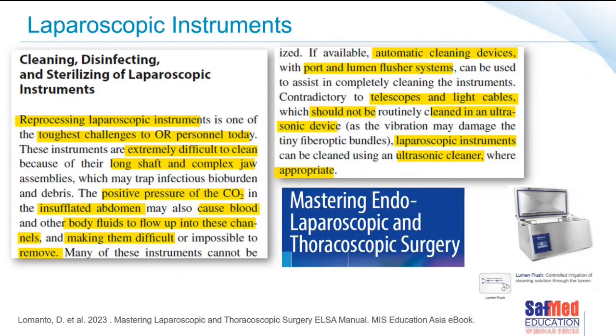Or in some cases, of course, you can use a special rack inside your automated washer disinfector that also has the ability to attach to the ports of your laparoscopic instruments. So not just lying them flat in a washer disinfector, but very specific racks that are designed for that type of instrumentation. Remembering, of course, that telescopes and light cables do not go in ultrasonic cleaners.